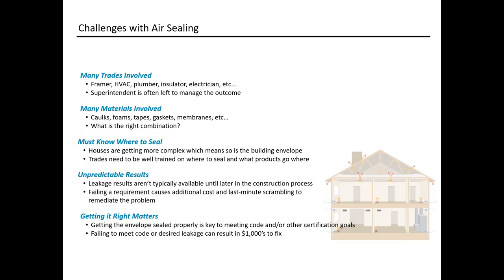The big drivers of why this is important: with standard practices there are a lot of unpredictable results. Although you're trying to achieve 3 ACH to meet code, you don't know what you'll get at the end of the process, and you don't know where the failures are until you do a blower door test. Getting it right matters — air leakage is going to impact your MEP, your mechanical system, and your insulation. Air moving through fiberglass or blown-in insulation will actually deteriorate the R-value. So when designing buildings with a set ACH in mind, other things may not perform as expected if leakage is more than anticipated.